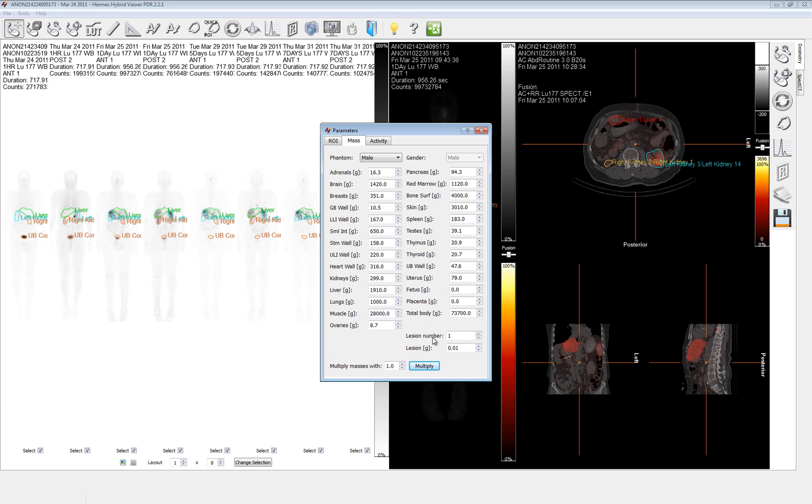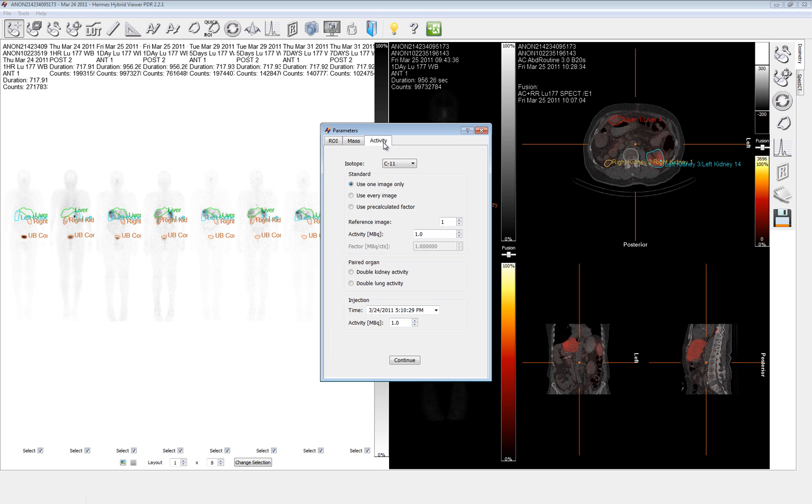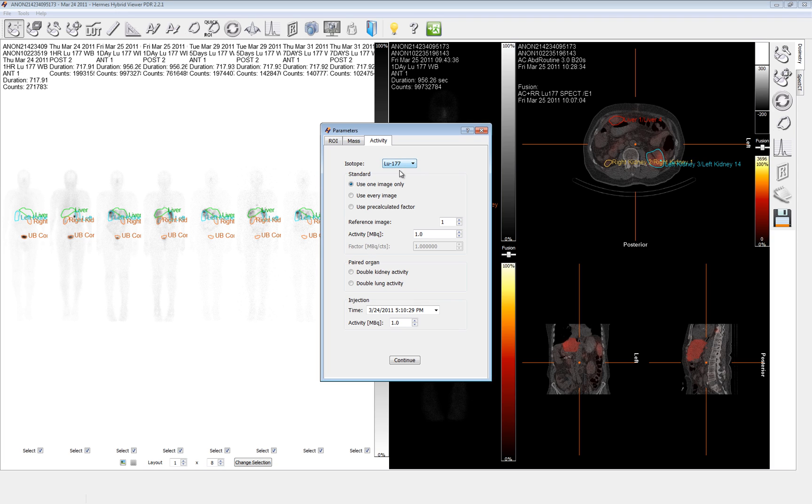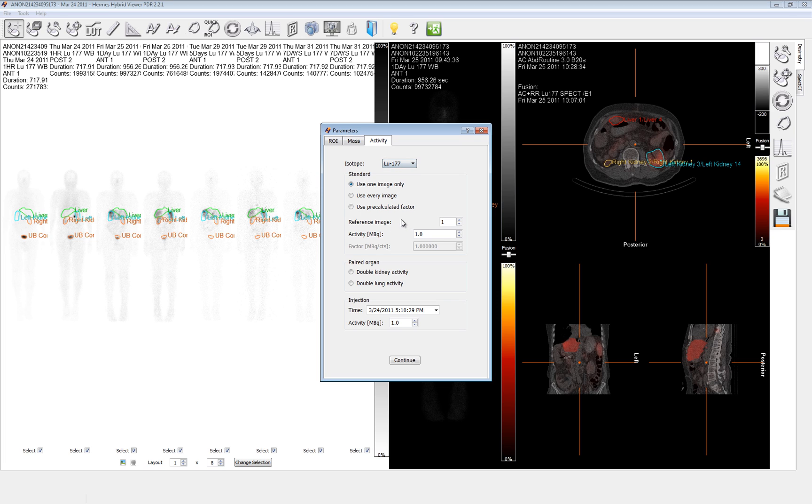So we are artificially making the organs a lot larger when we do that. I would potentially either change individual organs based on what you know from the volume and a known density or leave them as they are. The last tab here is the activity tab. This is where we can choose our different isotopes and as we know from earlier this is Lutetium-177. You can see that we've got a very good start to many of the isotopes most commonly used. As I stated earlier, we can add more so if you don't see yours, don't panic, just let us know.